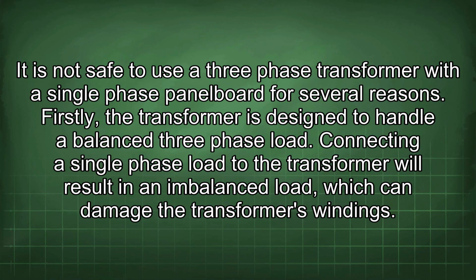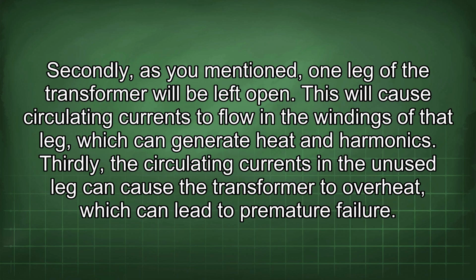It is not safe to use a three-phase transformer with a single-phase panel board for several reasons. Firstly, the transformer is designed to handle a balanced three-phase load. Connecting a single-phase load to the transformer will result in an imbalanced load, which can damage the transformer's windings. Secondly, as you mentioned, one leg of the transformer will be left open.